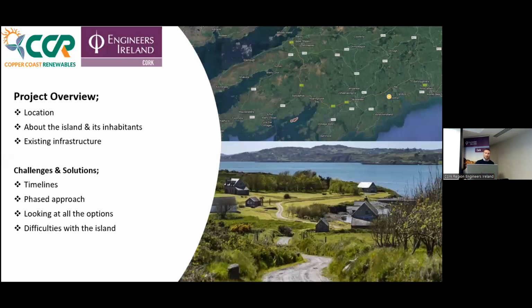Under phase one, we managed to take the diesel generator from 24/7 down to only 8 hours a day. We charged the batteries and got the old charge controllers up and running. Some batteries were end of life, discharged beyond recovery, so we didn't replace them since we knew we were doing phase two with solar. We just recoupled them and got the system recommissioned and running with the new settings.